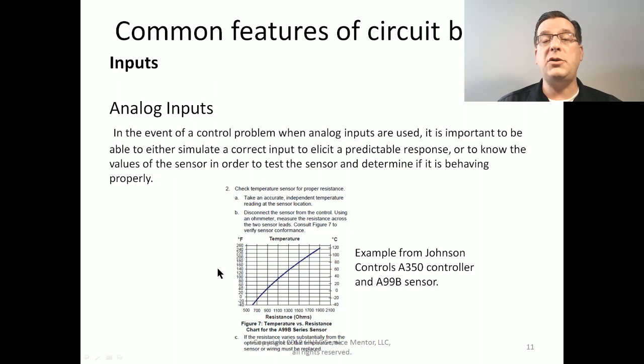A thermistor will change its resistance based on the temperature that it's exposed to. So, for example, here is a specific temperature sensor from a Johnson Controls A350 controller, which is a remote type thermostat, and the sensor is an A99B that's connected to it. For that sensor, say if it's experiencing 120 degrees Fahrenheit, it should be outputting a resistance of somewhere between 1100 and 1300 ohms, or maybe around 1200, 1250. So what I would want to do is measure the temperature that it's experiencing and then measure its resistance to determine if the sensor is working correctly.